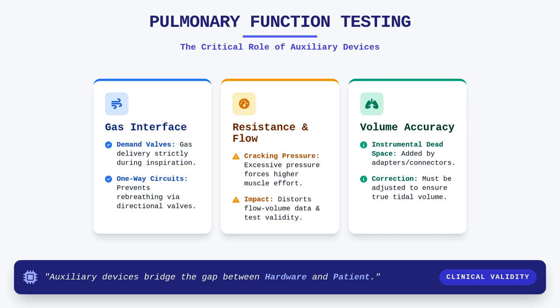If a valve has an excessively high cracking pressure, the patient must exert significantly more inspiratory muscle force just to open the mechanism, which inherently alters the resulting flow volume data and complicates the validity of your testing results. We also need to consider the physical dead space introduced by various adapters and connectors, as any additive volume in the breathing circuit effectively increases the instrumental dead space that the patient must ventilate. This contribution must be recognized and, when necessary, corrected during the data processing phase to avoid misrepresenting the patient's actual tidal volume or alveolar ventilation.